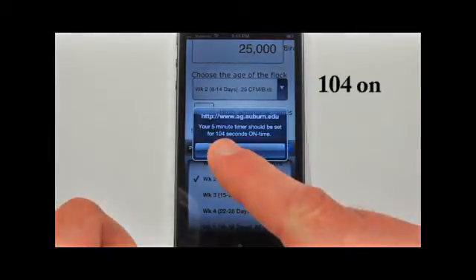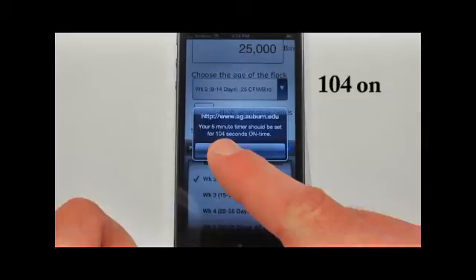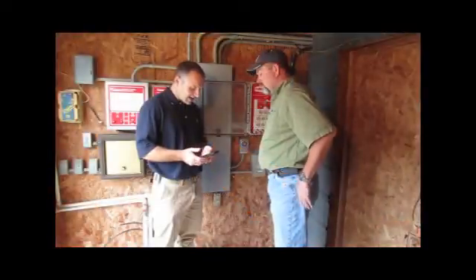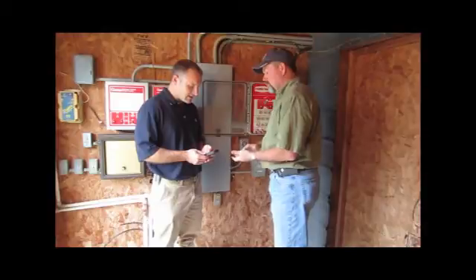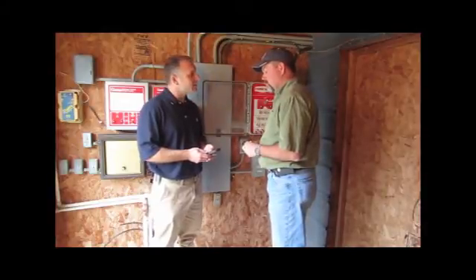The calculator suggests the starting point for minimum ventilation fan runtime should be set to a minimum of 104 seconds on out of five minutes. Remember, this is only a starting point, with the assumption that litter and air quality is ideal for rearing chicks. This calculator says you need a minimum of 104 seconds of on time.